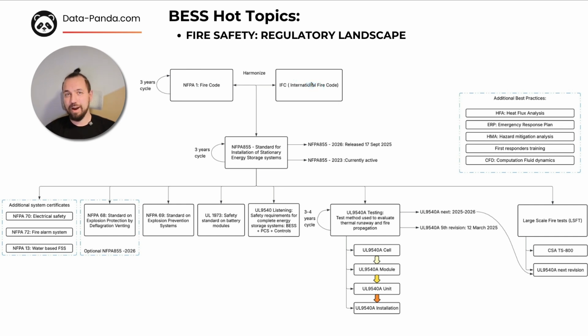And you will see that codes in other countries are also harmonized with IFC as a main body, like the main fire code. And these codes rely heavily on dedicated standards, specifically written for energy storage systems. That standard is NFPA 855, the standard for the installation of stationary energy storage systems. So NFPA 855 defines how BESS must be installed, including requirements for system spacing, fire detection, explosion prevention, ventilation, and emergency response planning. The current active edition of NFPA 855 is 2023, with the 2026 revision just being released.